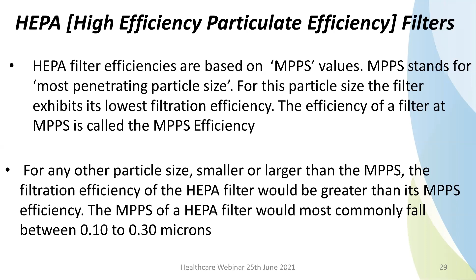So just try to correlate it to this COVID virus, because that is what affects us day in and day out these days. Most viruses, including this CoV2, range from 0.004 micron to 1 micron. And we are talking of 0.3 micron in your HEPA. However, viruses are rarely observed as individual particles. This is something you have to keep in mind. Instead, they are expelled from the body already combined with water, proteins, salts, and other components as large droplets and aerosols. Thus far, SARS-CoV-2 has been observed in aerosolized particles in a spectrum of sizes from 0.25 to 0.5 micron. With this, the use of HEPA filter is considered quite adequate to take care of this virus, even the COVID SARS-2.